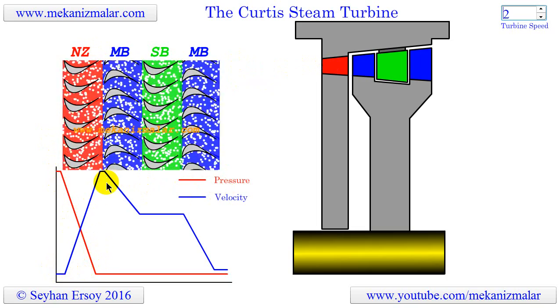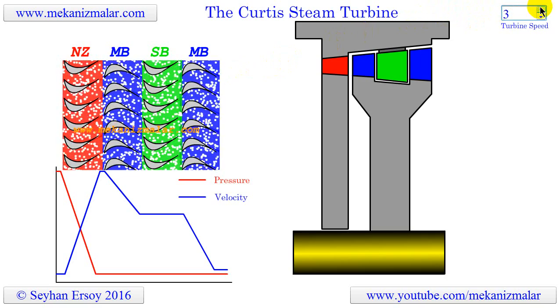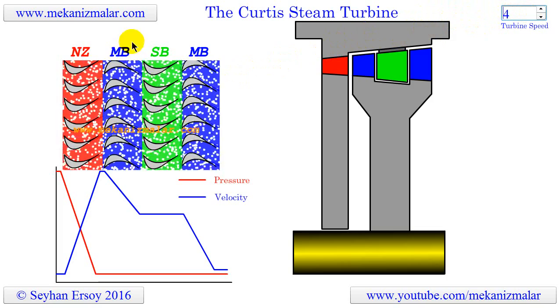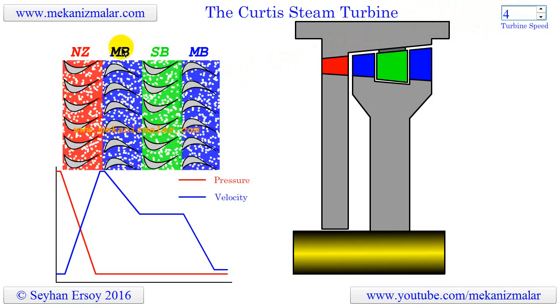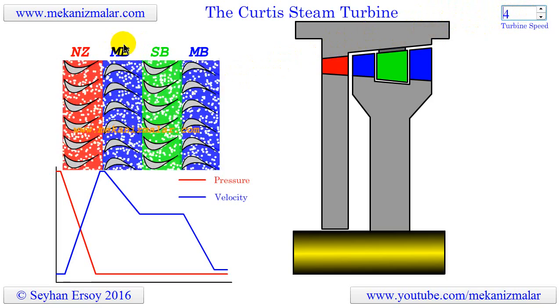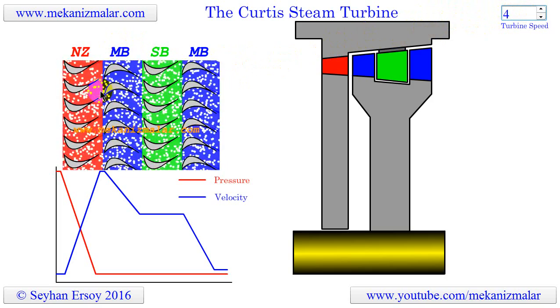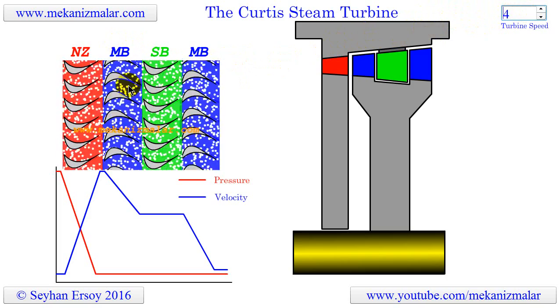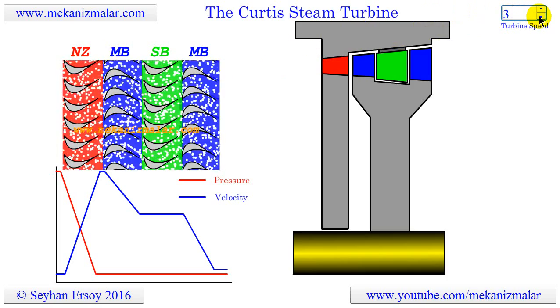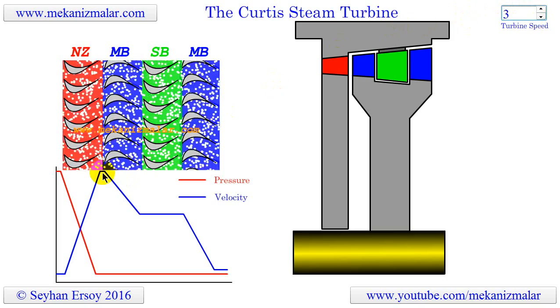The next stage, shown in blue, corresponds to the first action stage with moving blades, indicated by MB. The steam coming at high speed from the nozzles hits the moving blades and pushes them forward. During this process, the direction of the steam changes and the kinetic energy of the steam is converted to mechanical energy. As a result, the velocity of the steam is reduced in this stage, as seen in the plot.